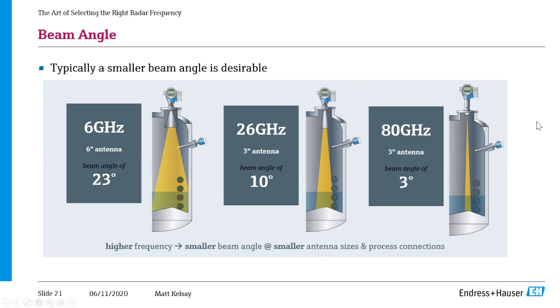Going to the next now, with an 80 gigahertz radar, we keep that same 3-inch size antenna, but now we've shrunk the beam angle down to 3 degrees. So beam angle, I'll say, is probably the biggest thing, or the biggest benefit to a higher frequency radar. Typically, a smaller beam angle is desirable, and that's because it makes commissioning much, much easier. You can see in the picture, if that signal's not hitting any of the obstacles in your tank, that means there's no false reflections coming back. You don't have to program the radar to ignore them.